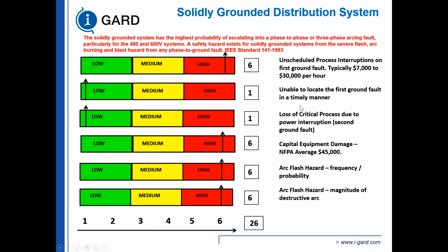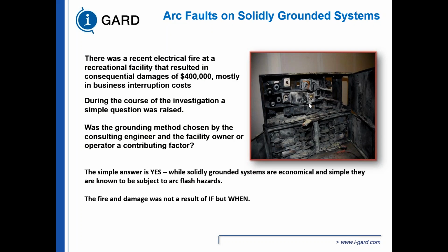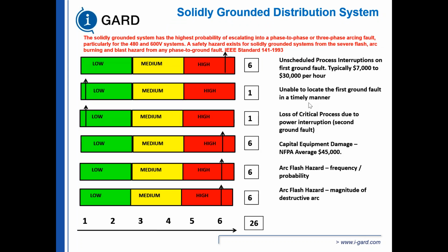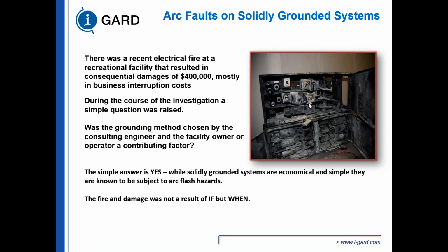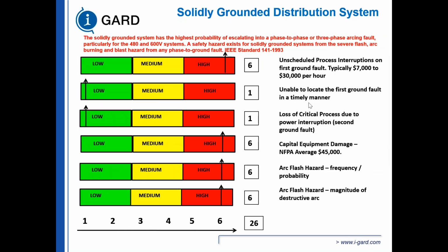Unable to locate the first ground fault in a timely manner. Well, the owners didn't find the first ground fault in this location until the entire system caught on fire. Loss of critical process due to power interruption. That's very low because you're never going to have a second ground fault. This was caused by one ground fault.